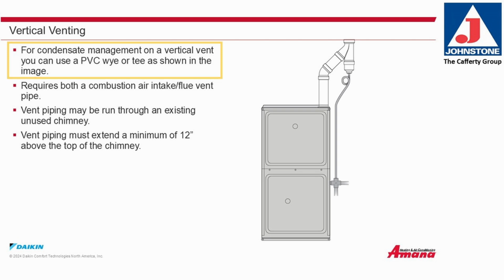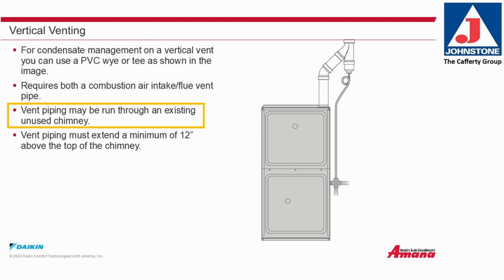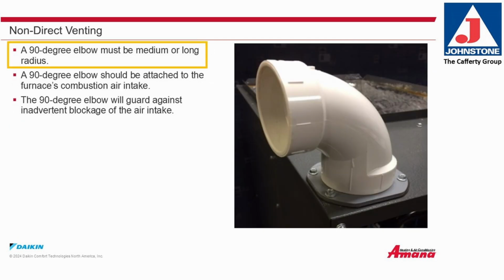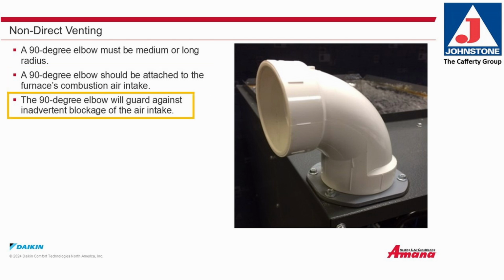Vertical venting. For condensate management on a vertical vent, you can use a PVC Y or T as shown in the image. It requires both a combustion air inlet and a flue vent pipe. Vent pipe may be run through an existing unused chimney. Vent piping must extend a minimum of 12 inches above the top of the chimney. Non-direct venting: a 90-degree elbow must be medium or long radius. A 90-degree elbow should be attached to the furnace's combustion air intake. The 90-degree elbow will guard against inadvertent blockage of the air intake.